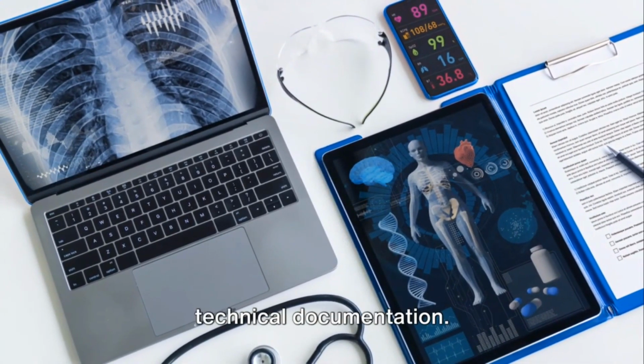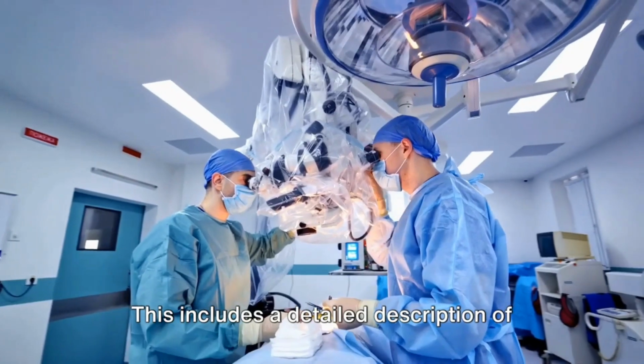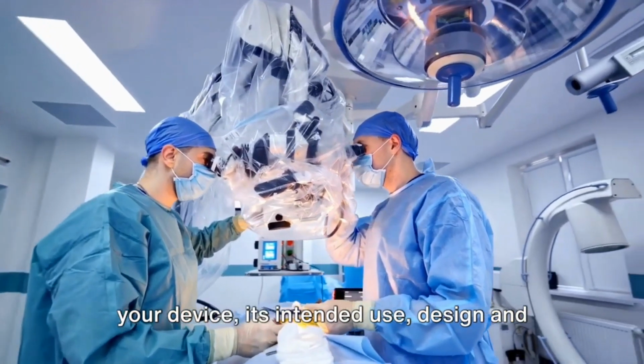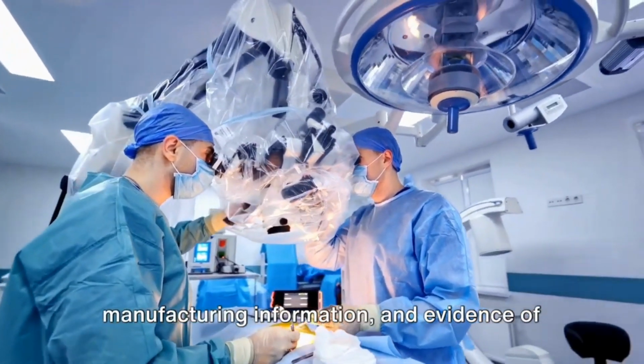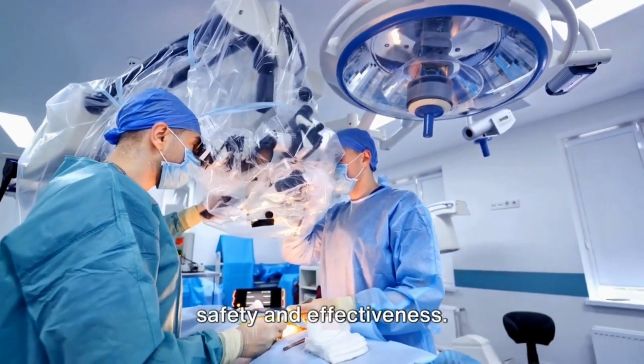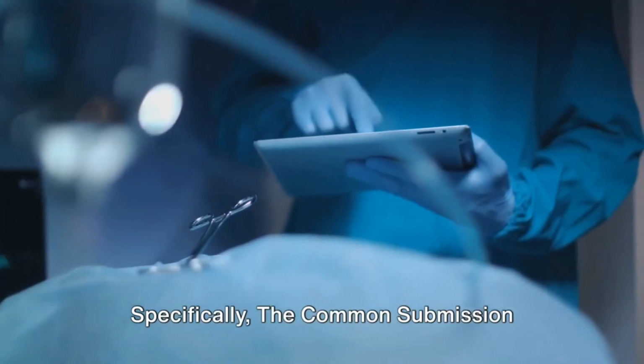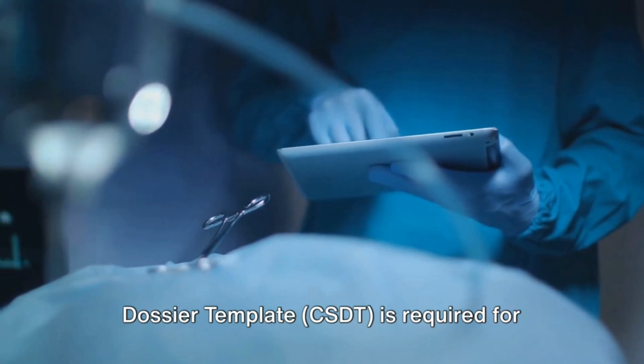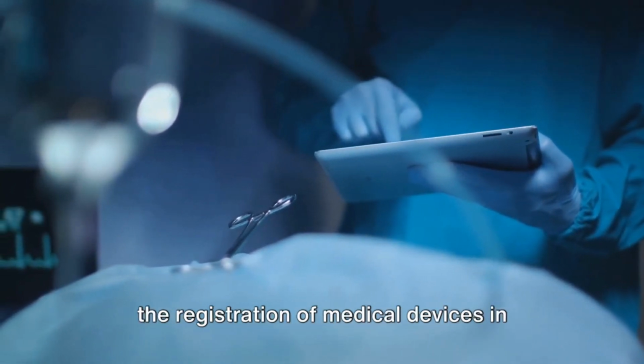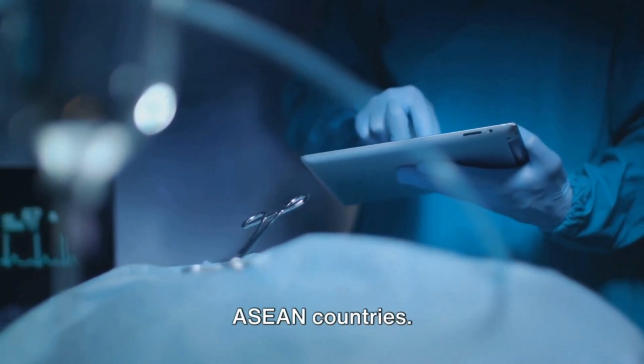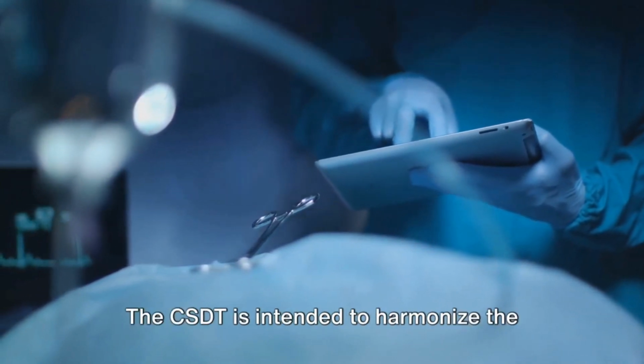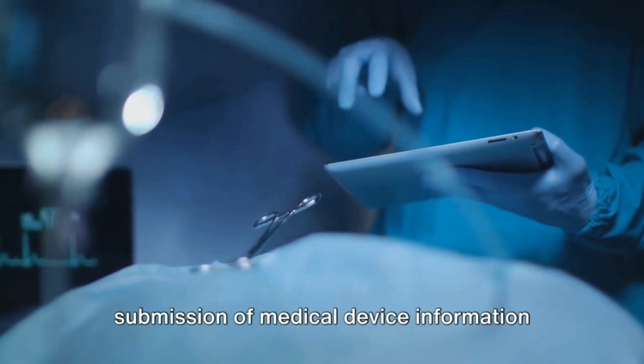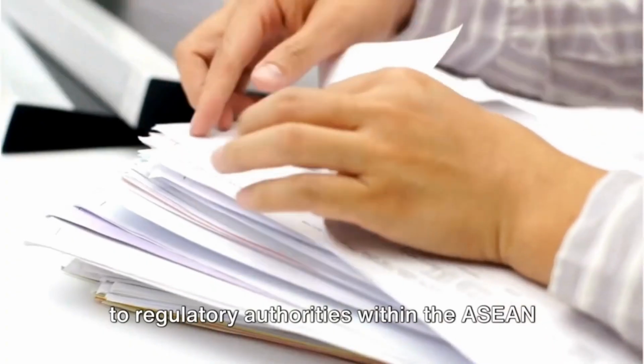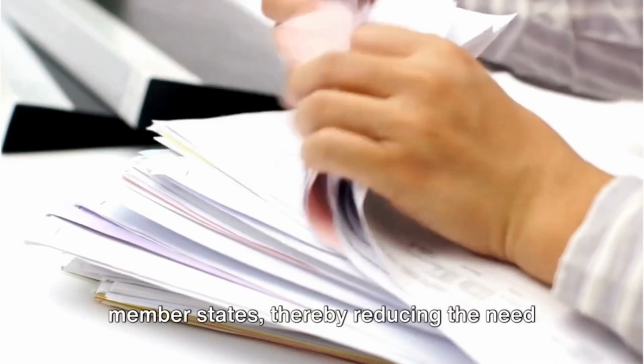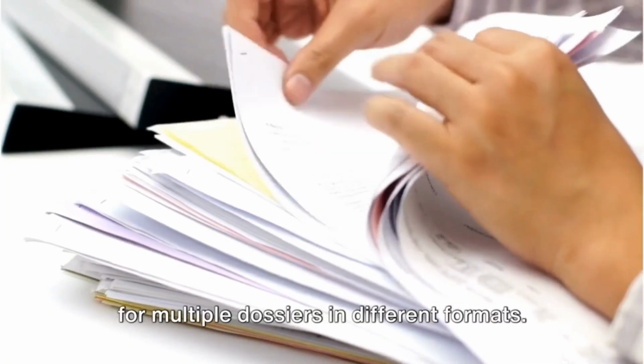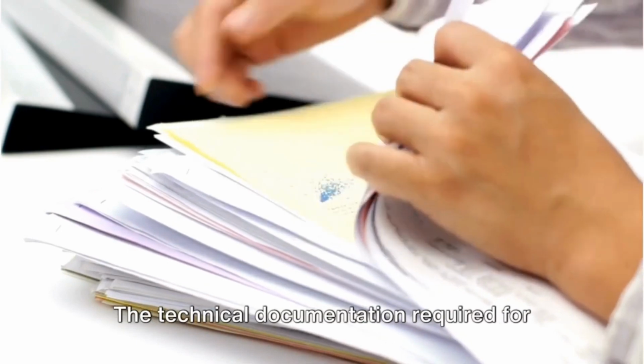Next, you need to prepare your product's technical documentation. This includes a detailed description of your device, its intended use, design and manufacturing information, and evidence of safety and effectiveness. Specifically, the Common Submission Dossier Template is required for the registration of medical devices in ASEAN countries. The CSDT is intended to harmonize the submission of medical device information to regulatory authorities within the ASEAN member states, thereby reducing the need for multiple dossiers in different formats.